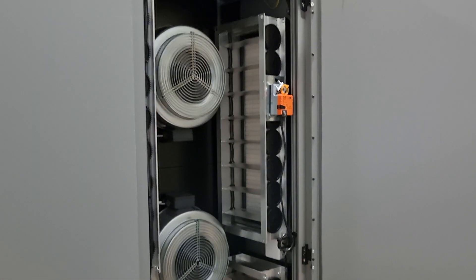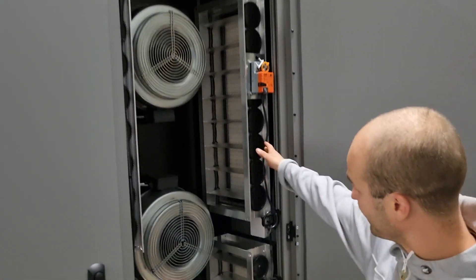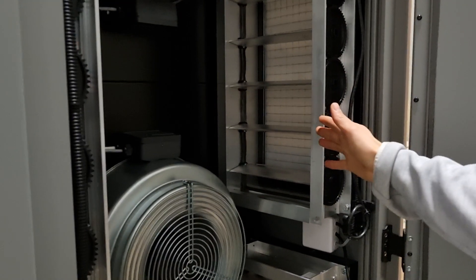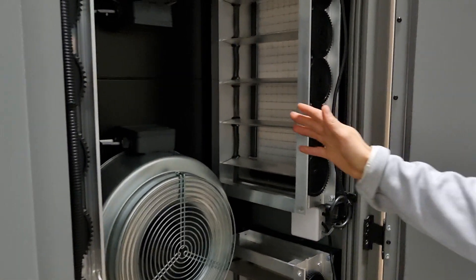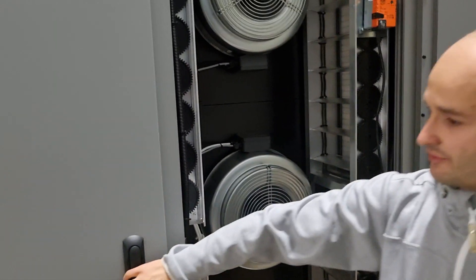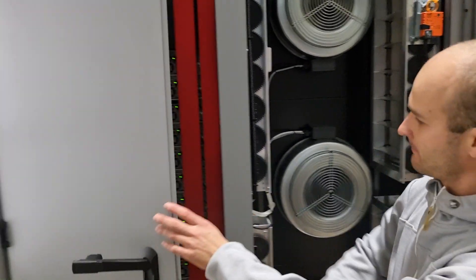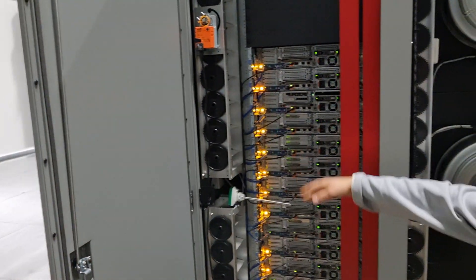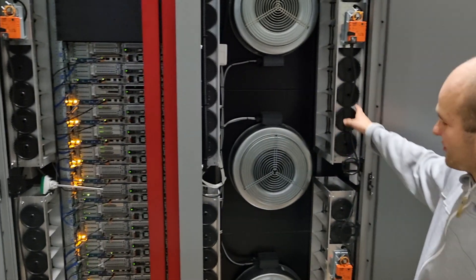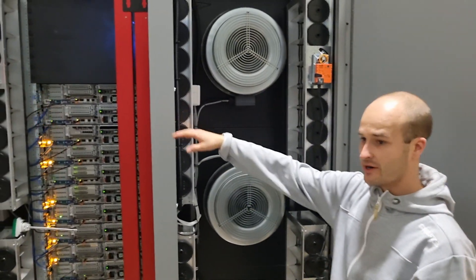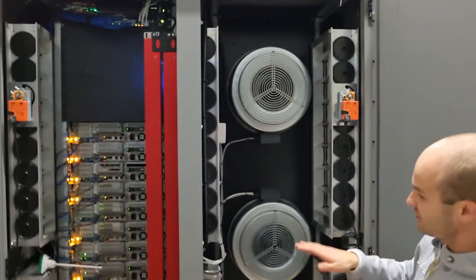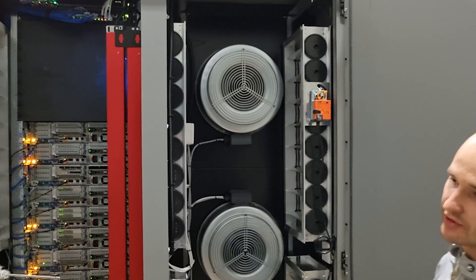This is the climate mixing chamber in the back here, where as I said the outside air comes in through the filters, and then there's an option to mix it with the return air from the servers. You can mix the cold air together with the warm air to get the desired temperature going into the rack of 23 degrees.